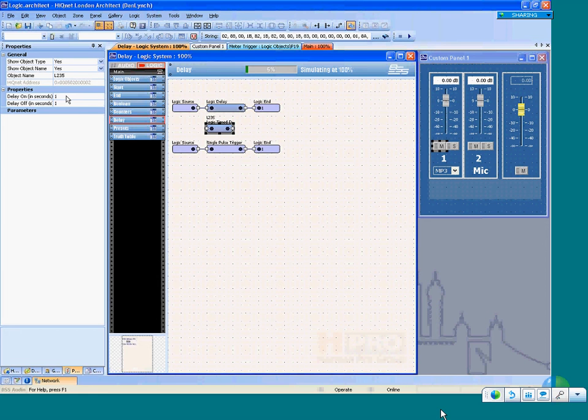So let's say your device is really busy and you try and set a 10-minute delay. Well, that 10 minutes is going to be wrong by up to 2, 3, 4, 5% by the time the logic delay gets done calculating it, because you could have that 2, 3, 4, 5, 6, maybe 10% overrun on every cycle.